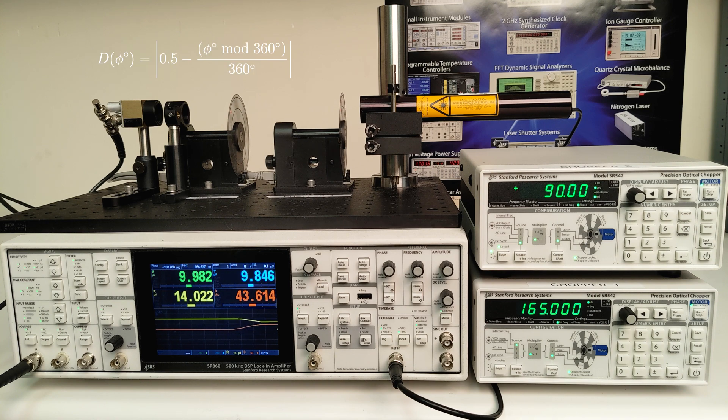You can calculate the duty factor using this formula, and can use that to generate plots of signal magnitude versus duty factor, for example, if you are searching for nonlinear effects in your sample.